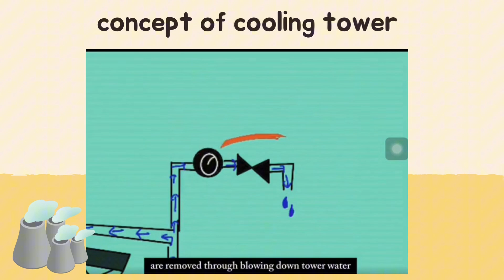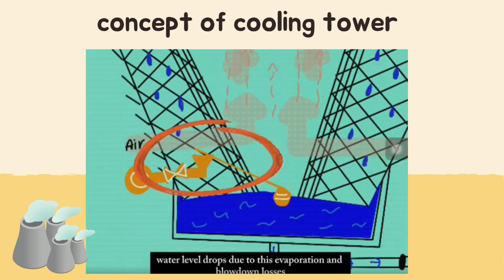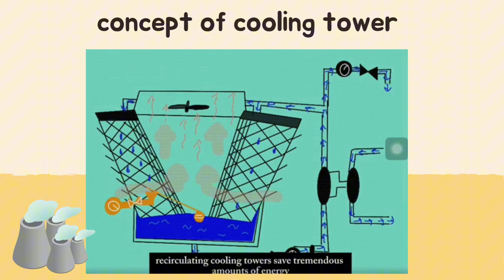Concentrated impurities in the tower are removed through blowing down tower water to drain. The basin water level drops due to evaporation and blowdown losses, and more makeup water is added to maintain levels. Open recirculating cooling towers save tremendous amounts of energy and reduce greenhouse gas.